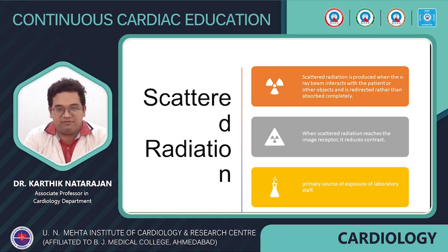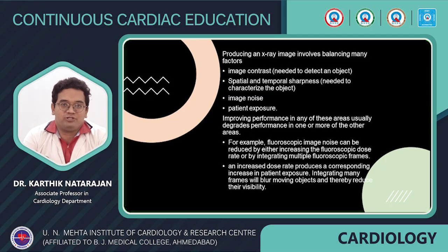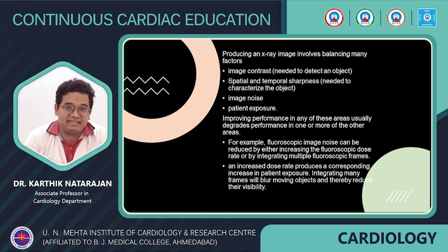exposure of laboratory staff. Producing an X-ray image involves balancing many factors: image contrast, spatial and temporal sharpness, image noise, and patient exposure. Improving performance in any one of these areas would degrade the performance in another. For example, if you want to reduce the image noise, you may have to increase the fluoro dose, or integrate multiple fluoroscopic frames.